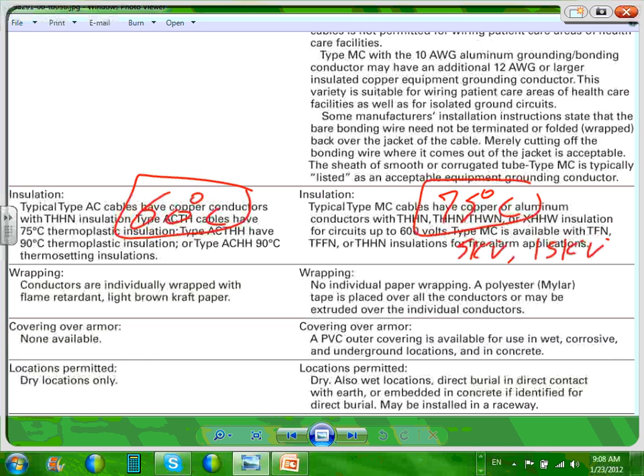Okay, so another advantage of MC cable, and I don't want to make an MC-AC fight here. Another advantage of MC cable, guys, you can have an MC cable that's rated for wet location. They have a jacket over MC cable rated for wet location. Most MC cable and AC cable are dry location. With MC cable, over the armor you have a PVC outer covering, available for use in wet location. Can you highlight that one? Wet location is a big deal.